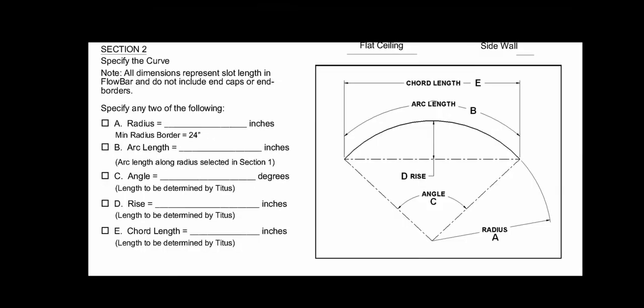The heart of any curved diffuser specification are the actual numbers, and many times the radius required is changed from the original spec, is being done outside a design spec, or the unit is a retrofit item. When it becomes necessary to provide a curved unit to suit, the radius and included angle may be difficult to obtain or to measure. Using the alternate dimensional specifications of chord length, arc length, or rise may be used if the radius and angle are not provided or cannot be effectively measured. Simply select two of any of the five dimensions and we will do the rest.